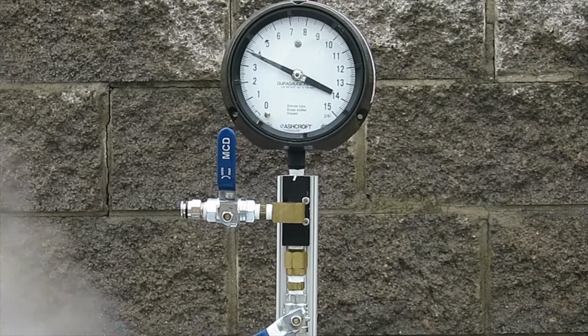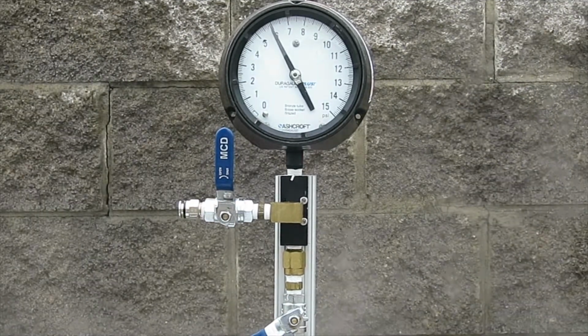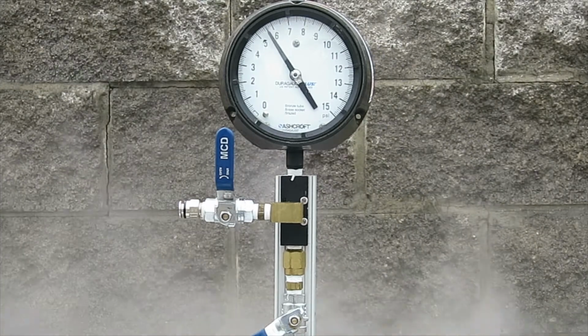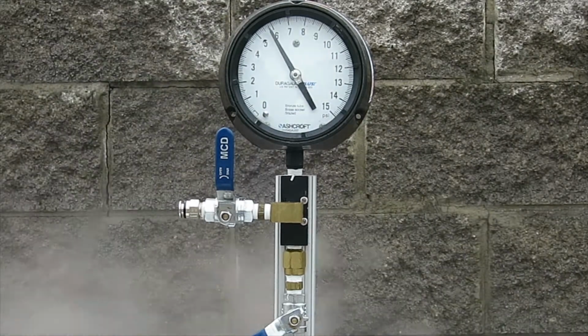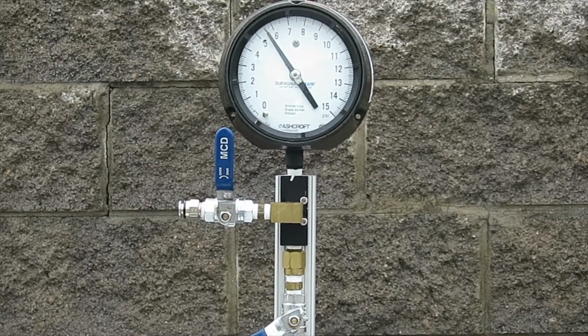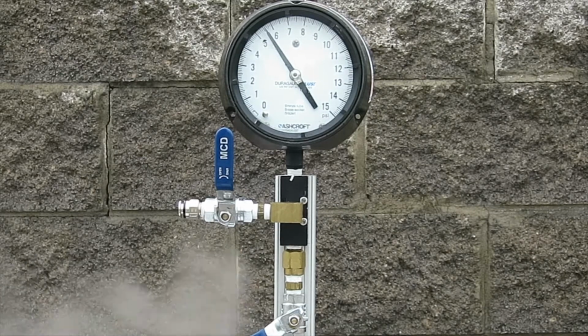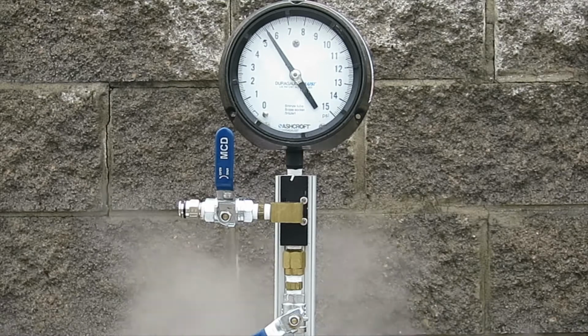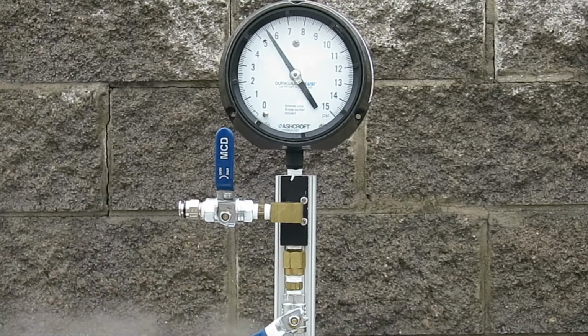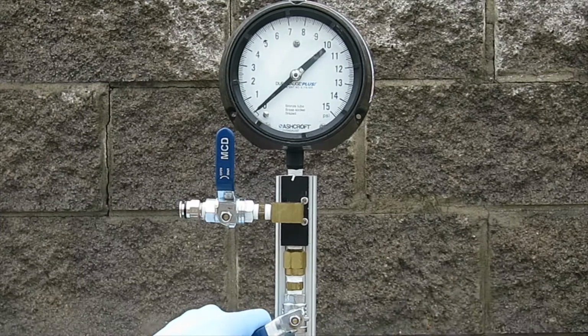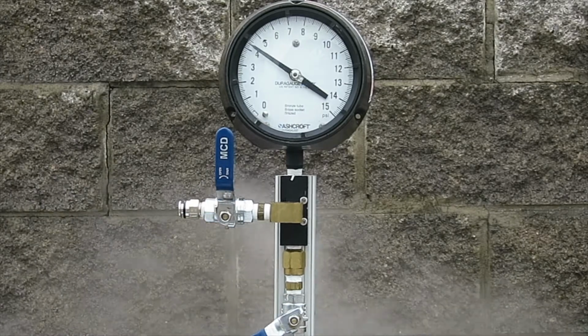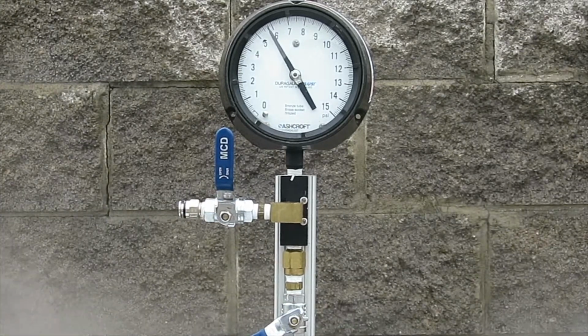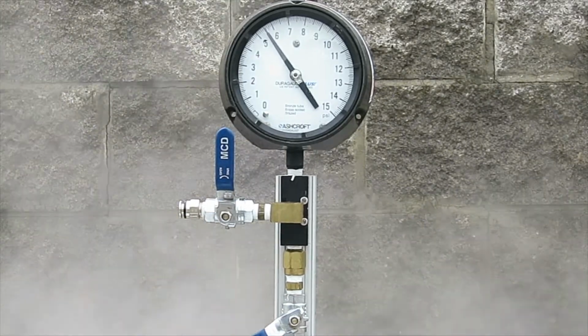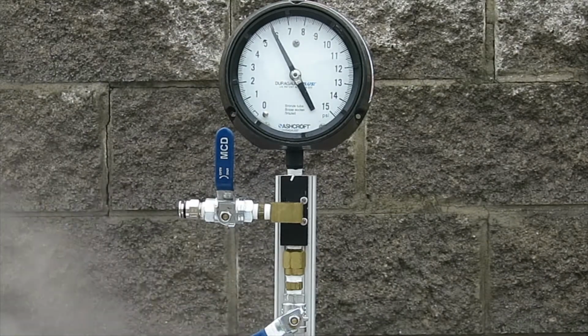Once you have established the 5.5 psi dynamic head pressure, you will need to record the fuel pressure, as well as the system pressure and temperature displayed on your front panel gauges. The equipment will need to maintain the system pressure and temperature in order to still be calibrated at 5.5 dynamic head pressure. We have found a variance of plus or minus 3 psi of system pressure will no longer produce a 5.5 psi dynamic head pressure.